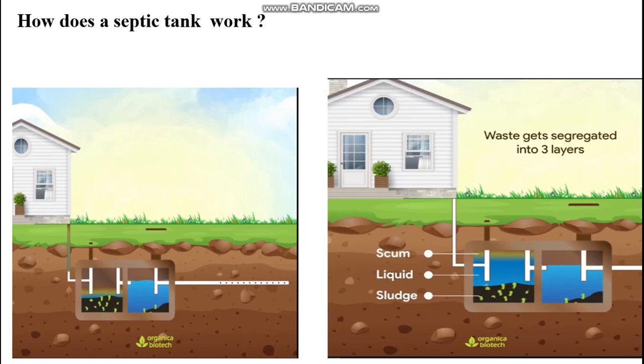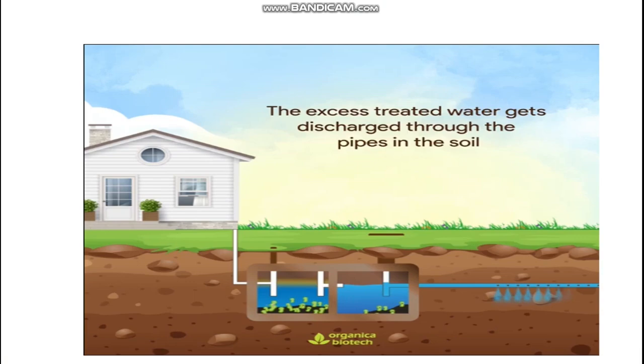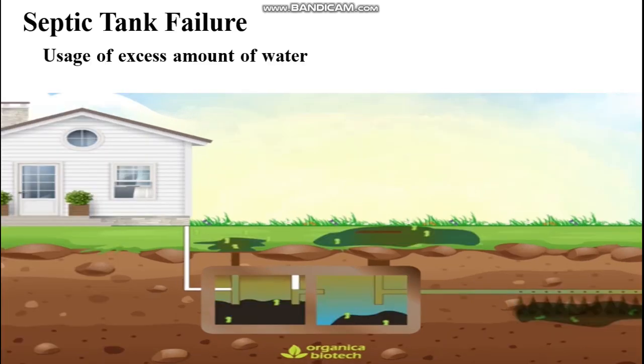How does a septic tank work? First, sewage is disposed from the house through the inlet pipe to the septic tank. Solids entering the first chamber settle to the bottom forming sludge, while lighter solids such as grease and organic waste float on top forming scum. Treated liquid enters the second chamber, known as effluent. Microbes naturally present in the tank degrade the sludge. The treated water passes through the baffle to the second compartment, and finally the treated effluent is discharged through perforated pipes to the leach field.